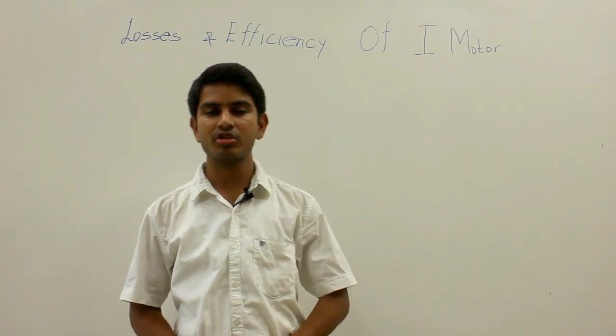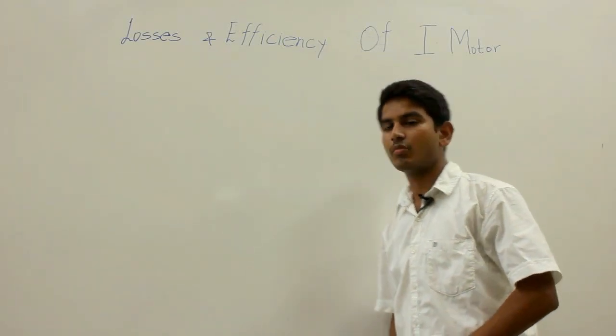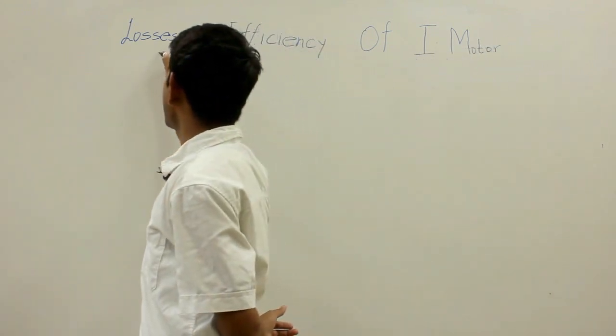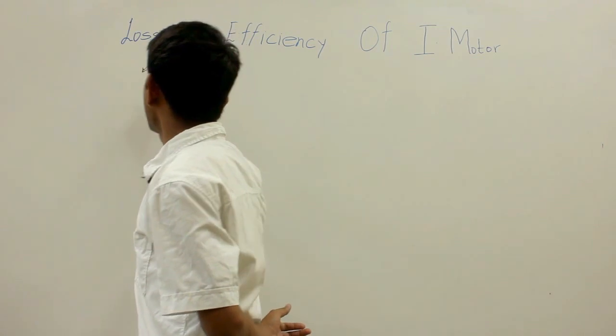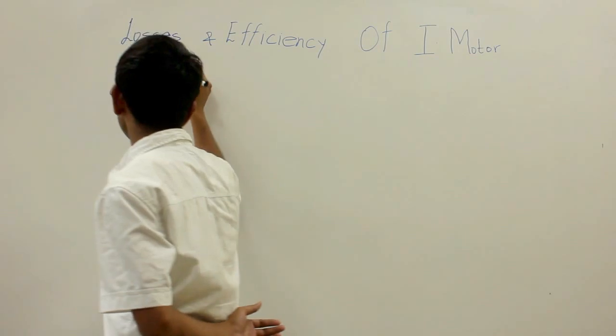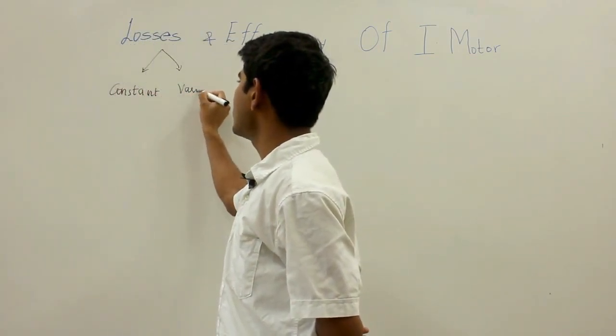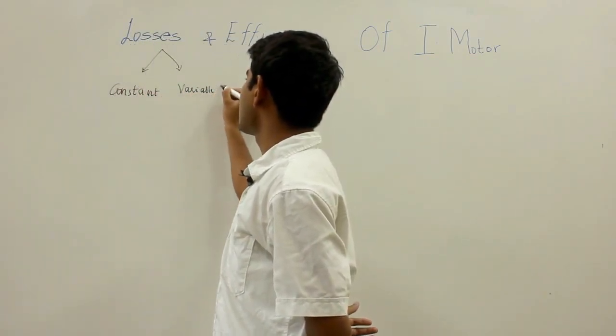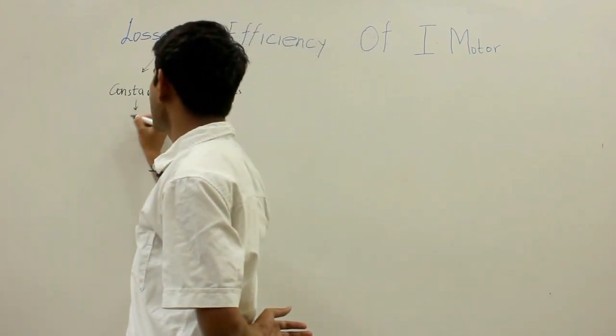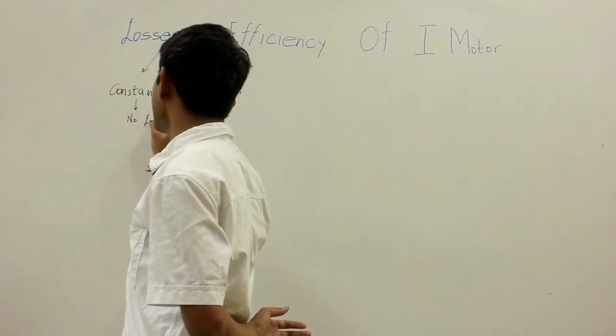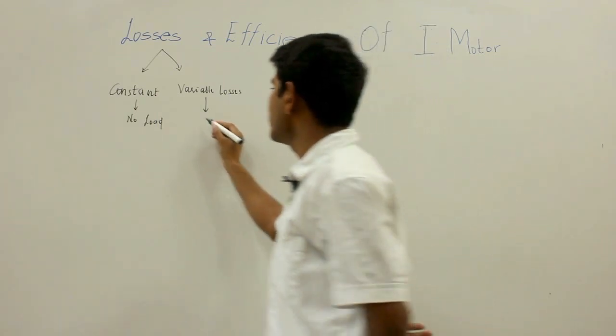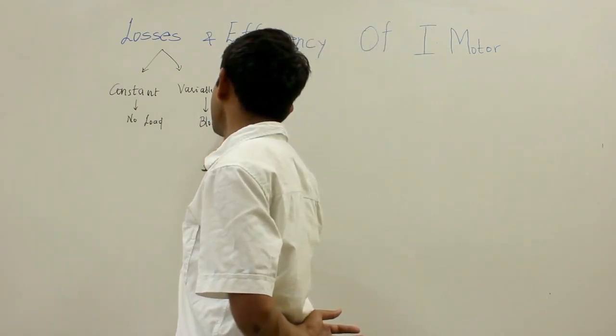In this video, let us discuss the losses and efficiency of an induction motor. There are basically two types of losses: constant losses (or fixed losses) and variable losses. The constant losses can be determined by performing the no-load test on the induction motor, whereas the variable losses can be determined by performing the block rotor test.